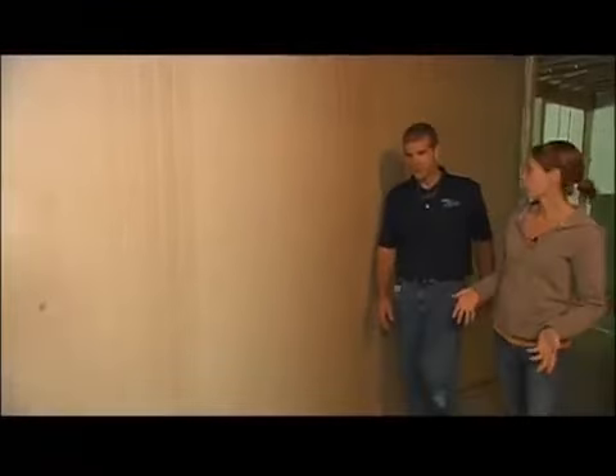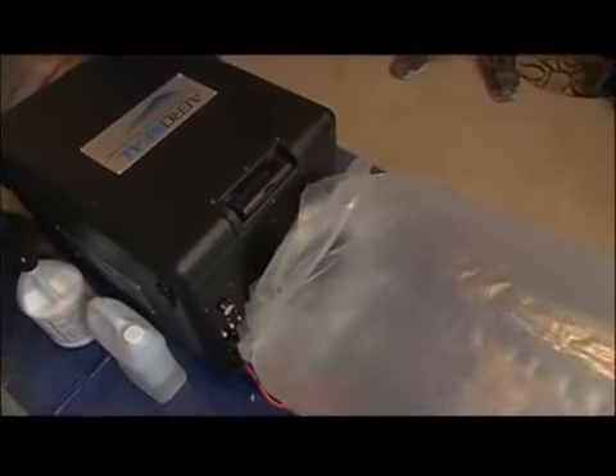Now everything's all sealed up upstairs, and you're going to do a pre-test? That's right—we'll turn on the system, pump air into the ductwork, and find out how bad the system really does leak. I do notice the system looks pretty well taped off. It may reduce the leakage a little, but I wouldn't be surprised if it leaks quite a bit. Let's find out.